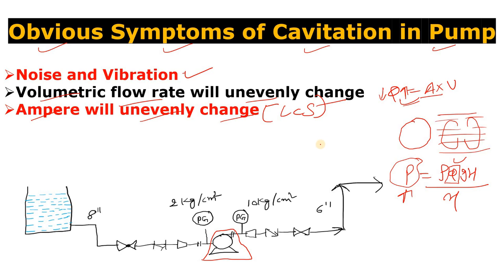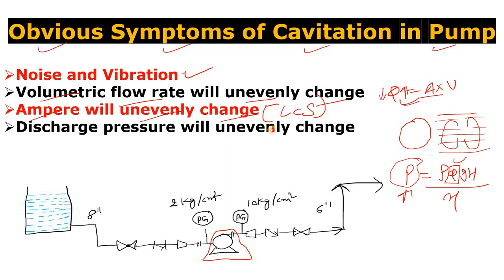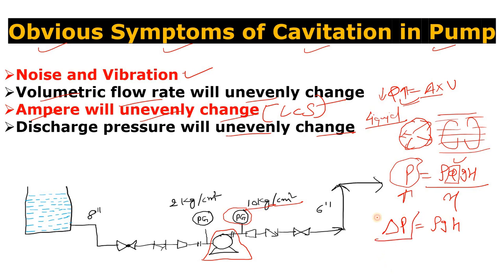The next symptom is that the discharge pressure will unevenly change. You can see here this is the discharge pressure gauge showing 10 kg per centimeter square. Using the formula delta P equals rho times g times h — as vapor bubbles form, the density of vapor is lower than that of liquid, so delta P will be low. The discharge pressure will unevenly change: it will increase, then decrease, then increase, then decrease — fluctuating in that manner.